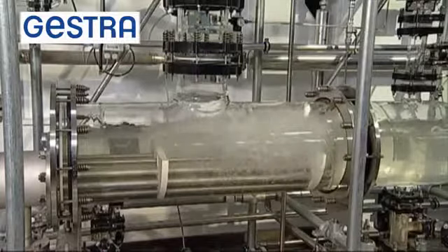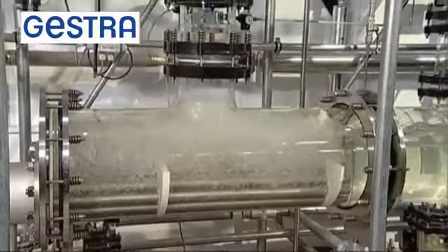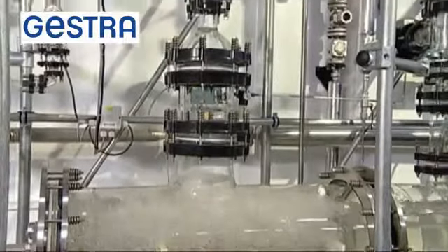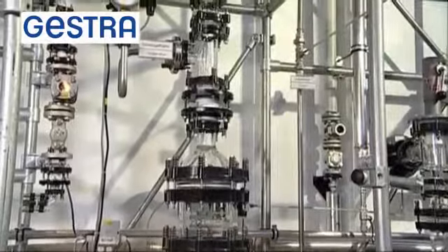This is a critical moment in the steam process because boiler water with a high conductivity then passes into the steam system. Priming leads to increased corrosion in the entire steam system, with all the consequences in terms of cost. To make matters worse, the steam loses heat because it's mixed with water. A kind of wet steam leaves the steam generator. This may lead to poor heating performance since the steam traps at the heat exchanger are not dimensioned for such quantities of condensate.